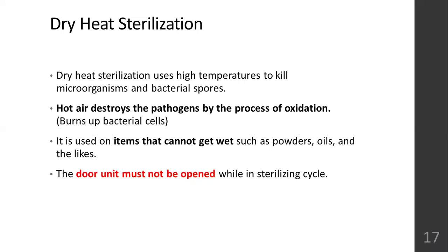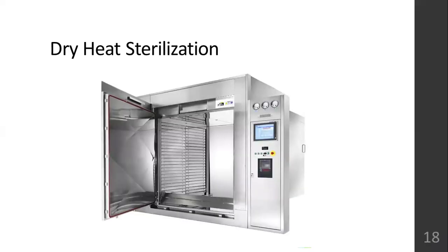When do you use the hot air oven? When you have items that, if they get wet, will not function, those kinds of instruments or items will go into the hot air oven, because you can't afford these items to get wet, like powders and oils. The door of the unit should not be opened immediately. You have to allow the hot air oven to cool down. Otherwise, if any glass items are kept inside and you open it immediately, the gush of cold air, the sudden change in temperature from hot to cold, can break the glass items or damage other items. So let the hot air oven cool down and then you can open it. This is how the hot air oven looks like.